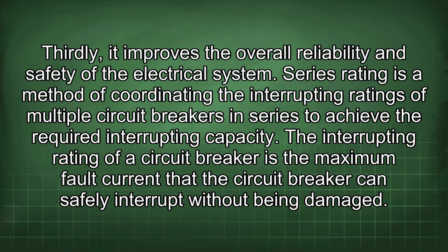Series rating is a method of coordinating the interrupting ratings of multiple circuit breakers in series to achieve the required interrupting capacity. The interrupting rating of a circuit breaker is the maximum fault current that the circuit breaker can safely interrupt without being damaged.